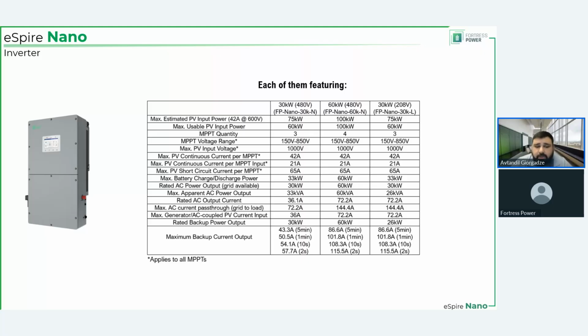These MPPTs, whether you have 3 of them or 4 of them, depending on the inverter type, are identical. So MPPT voltage range is the same, input voltage is the same, quantity of inputs per MPPT is the same, 2 per MPPT. And an MPPT can handle 42 amps of continuous current, but there may be no more than 20 amps of continuous current per input. And 1000 volts is the maximum PV input voltage, that is very straightforward. That's what you're allowed to have in the commercial application, and that's why the inverter, this being a C&I inverter, has to accommodate those 1000 volts as well.